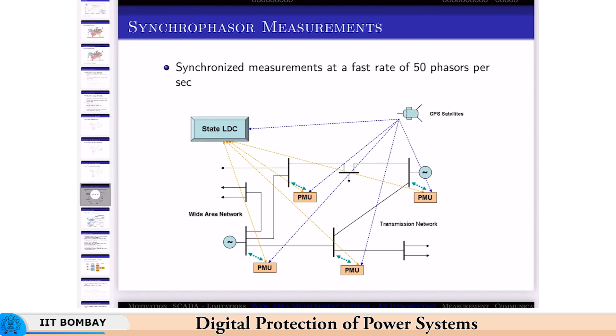So there are PMUs installed, one PMU or multiple PMUs depending on the number of channels. You get PMUs as basic relays functioning as PMUs, which can do 2 channels, that is one voltage and one current. So rather it is 6 channels, because you need 3 phases for 1 voltage and 3 phases for 1 current, and then that can go up to 36 channels. So 12 phasors can be monitored. So this is the setup, and the communication backbone is usually fiber optic, because you need a fast, very low latency kind of communication network.